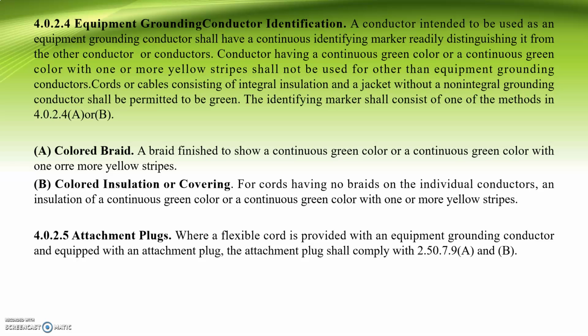Chapter 4.0.2.4, so equipment grounding conductor identification. So a conductor intended to be used as an equipment grounding conductor shall have a continuous identifying marker readily distinguishing it from the other conductor or conductors. So a conductor having a continuous green color or a continuous green color with one or more yellow stripes shall not be used for other than equipment grounding conductors. So cords or cables consisting of integral insulation and jacket without a non-integral grounding conductor shall be permitted to be green. So the identifying marker shall consist of one of the methods in chapter 4.0.2.4 A or B.